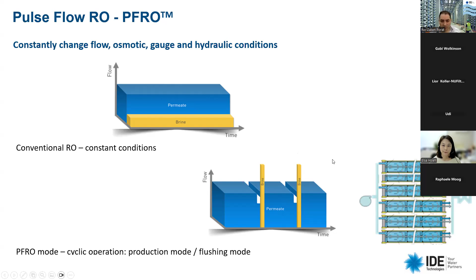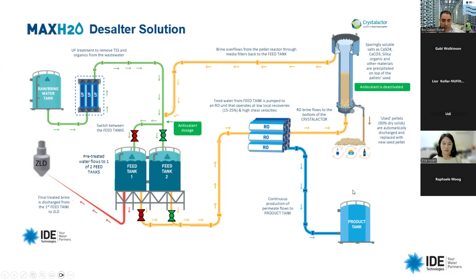The other technology is the Max H2O desalter, which allows reaching very high recovery, overcoming scale by precipitating it out in a fluidized bed reactor. This is again a patent of IDE that we developed with a Dutch company, Royal Haskoning DHV. It's essentially a reverse osmosis process in which the brine, oversaturated with salts such as silica, calcium fluoride, calcium carbonate, and calcium sulfate, is transferred to a fluidized bed reactor where the scaling solids precipitate on seeds, and the brine without those constituents is transferred back to the feed tank. The process continues, and we can reach 90, even 99% recovery of good water that can be used for various applications within the FAB, minimizing the water taken from the grid.